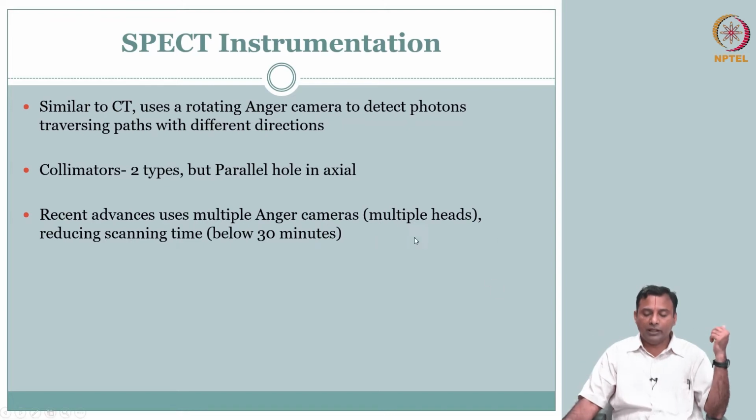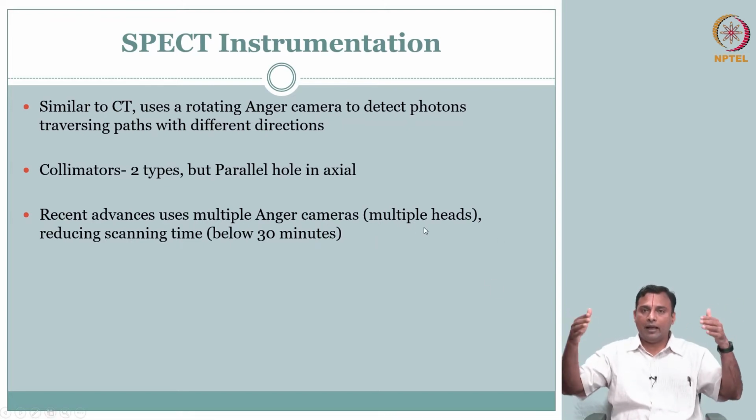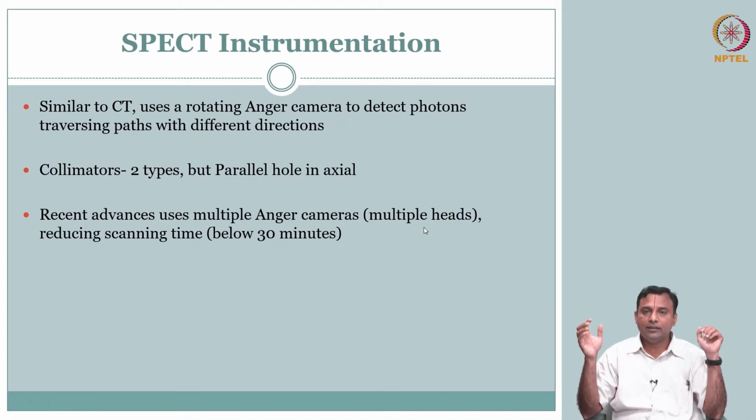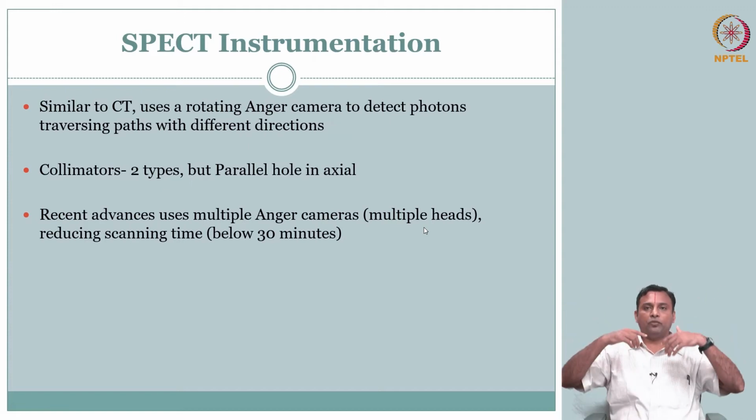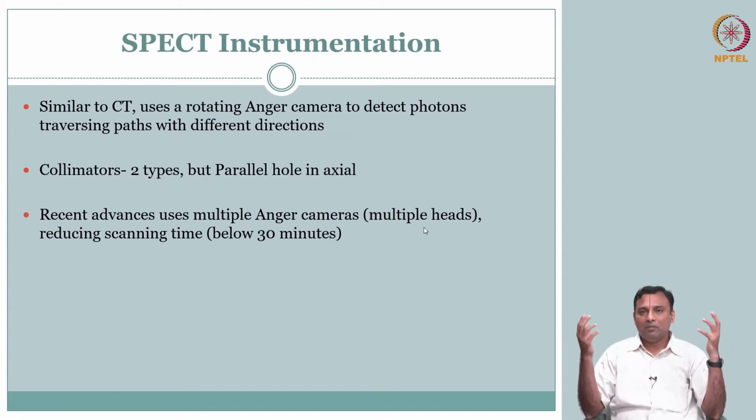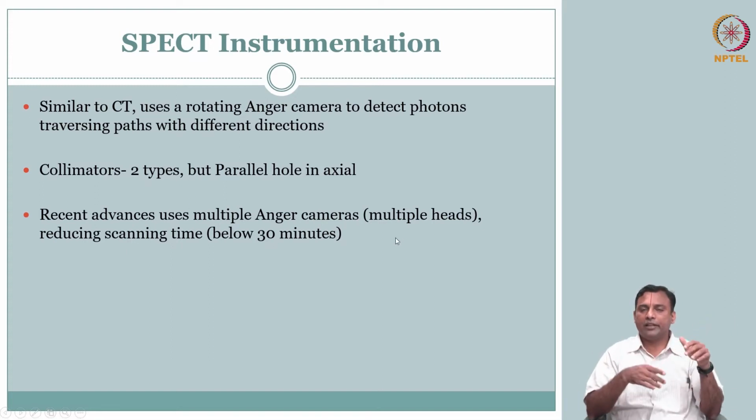So you could have multiple heads, meaning multiple planar gamma cameras at different angles, and you could record. But typically in that sense you could think about having it full throughout the body. But usually what they found is there's a trade-off, right? It becomes very cumbersome, very expensive to do all that. So usually two heads is reasonable, especially the configuration that I showed.